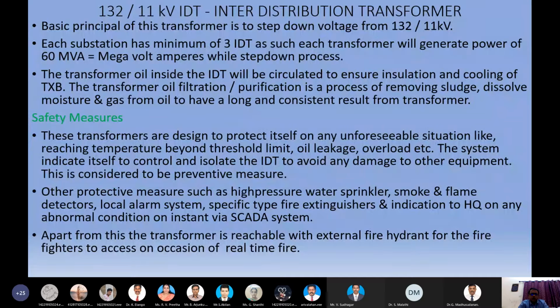So this indication will have an alarm sound to a radius of 2 to 3 kilometers, and the SCADA indications will be communicated to DIVA HQ instantly. And of course, specific fire extinguishers will be available, and any kind of indications, as I said, will be communicated to HQ. Apart from this, the transformer is reachable with external fire hydrants for the firefighters to access in the event of a real-time fire. The external fire hydrant is placed at a distance of 5 meters in either direction of each IDT, the transformers, and another fire hydrant is available at the exit and at the entry of the substation.